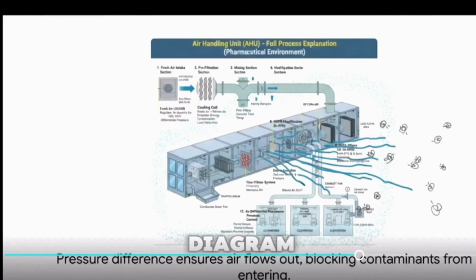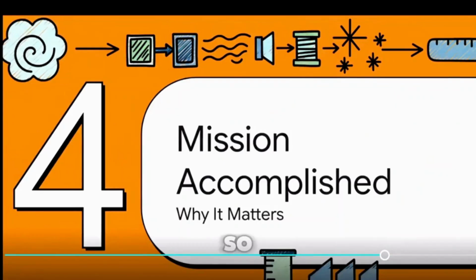Looking back at our diagram, you can see how this all comes together. When that super pure air is supplied to the clean rooms, it creates what's called a pressure cascade. What that really means is, anytime a door opens, the air flows out of the clean room, not in. It actively pushes any potential contaminants away. It's like a constant invisible force field protecting the entire sterile environment. It's brilliant.